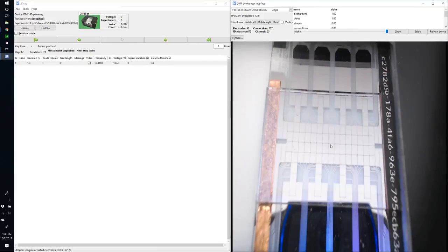and then you insert the device spacer underneath so it makes contact with the pogo pins. And I just have a white piece of plastic. You could use a white piece of paper as well to give yourself a nice surface to reflect. Because the chip is so reflective with the chromium layer, it helps to have an even background positioned against the camera so that you get a nice even lighting across the chip.